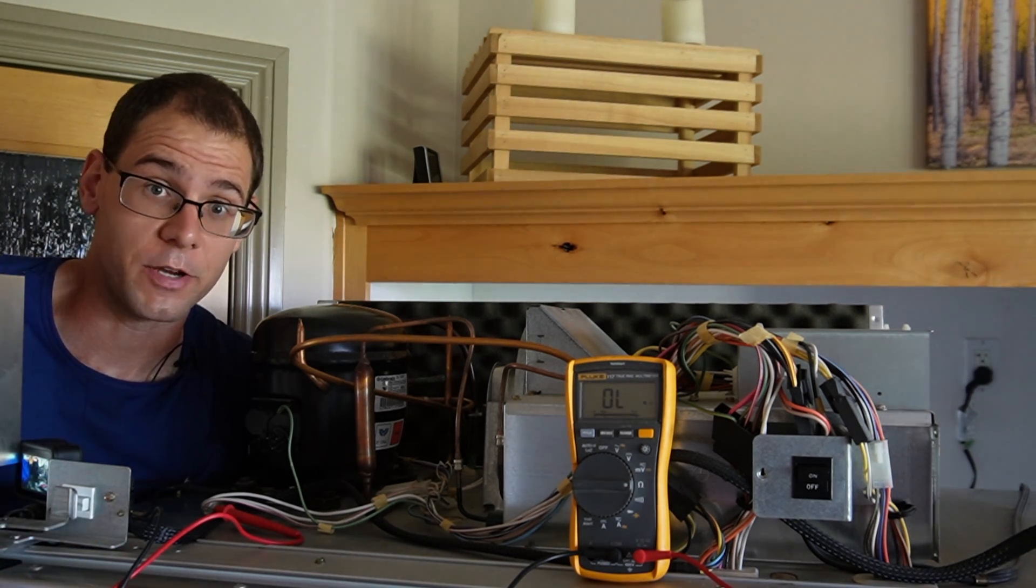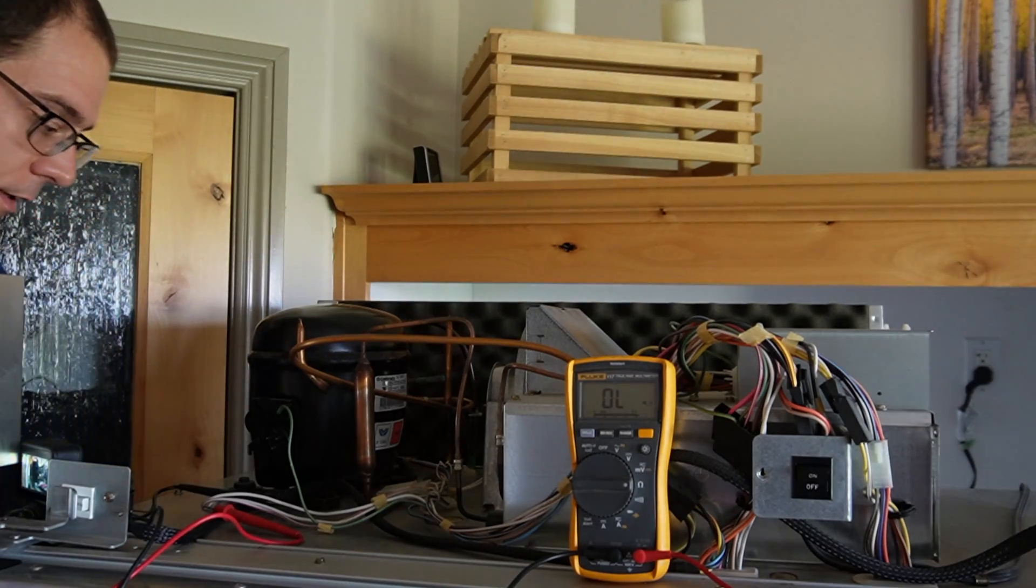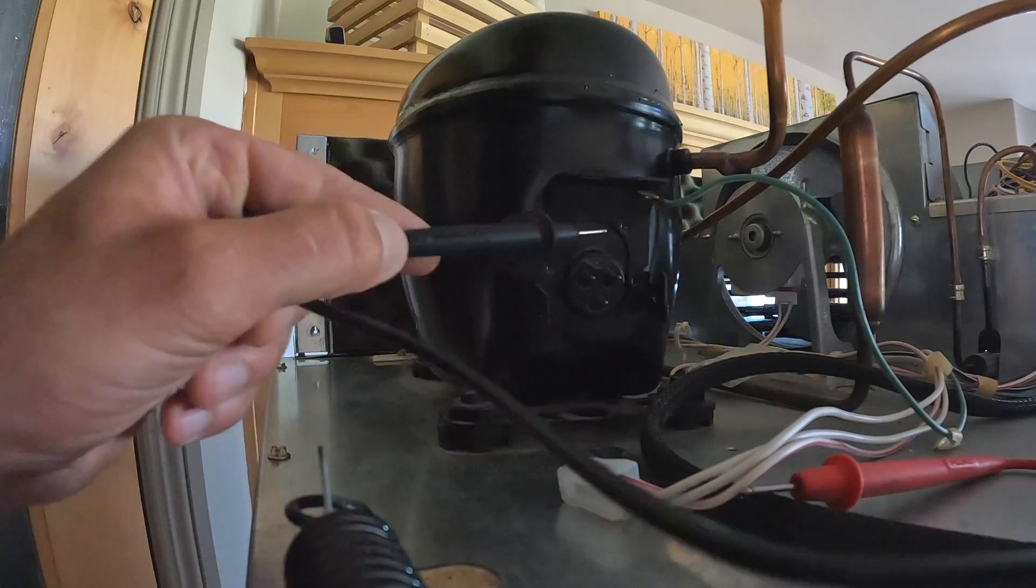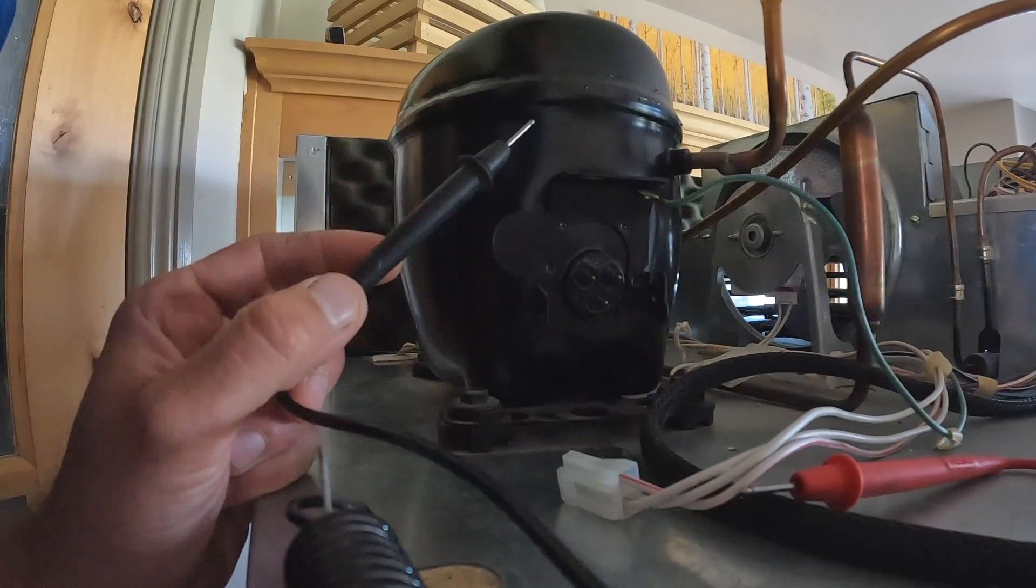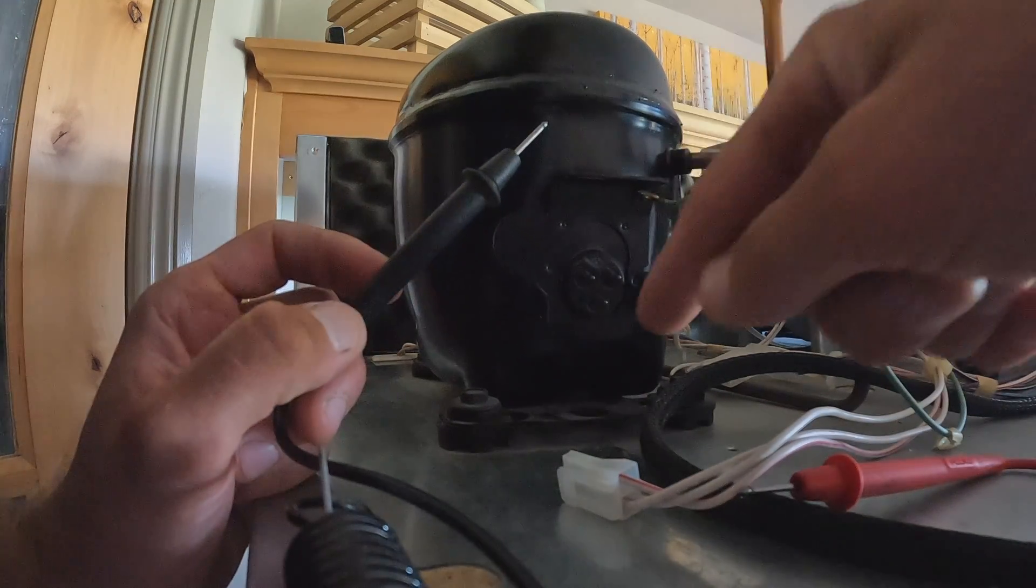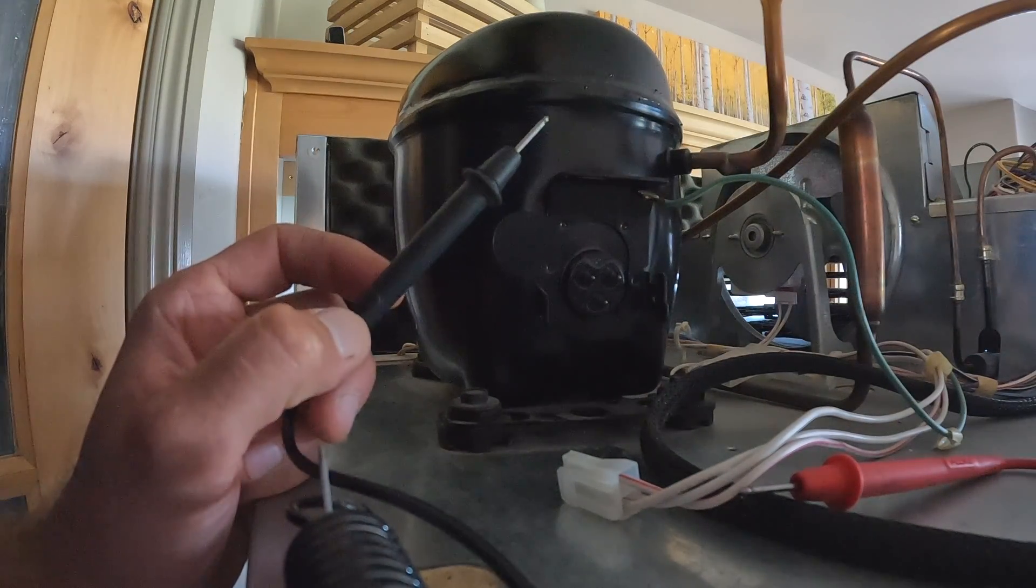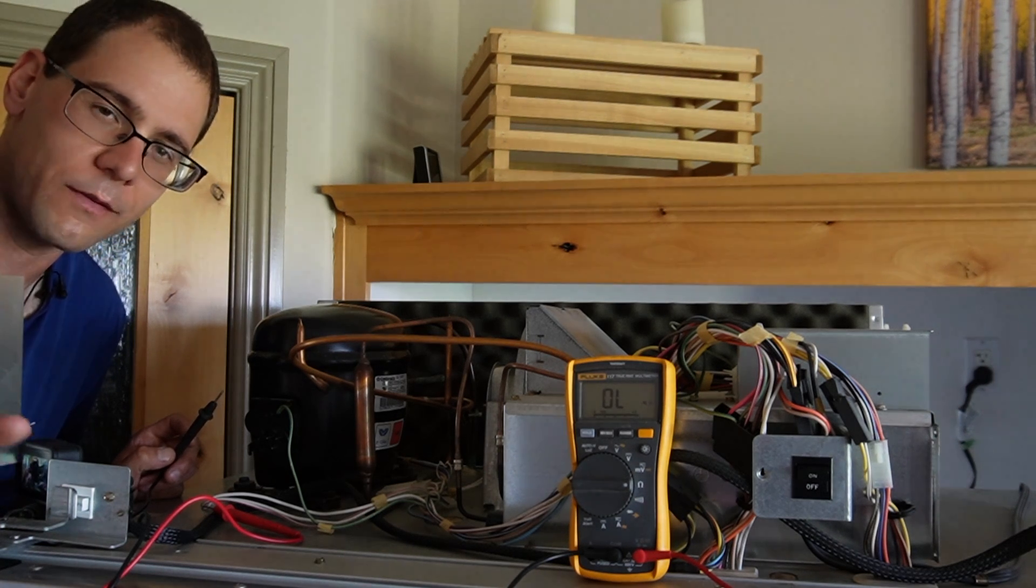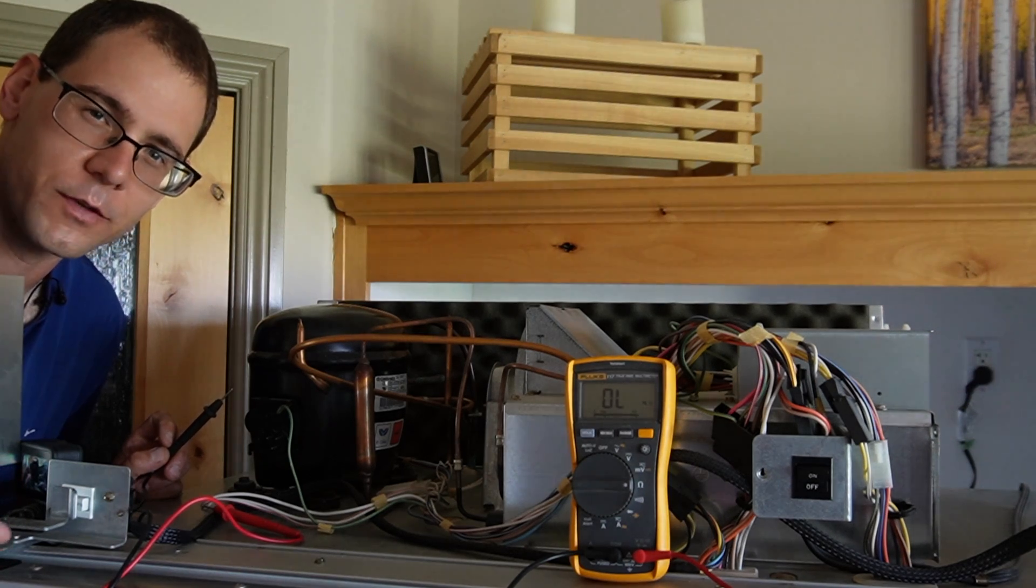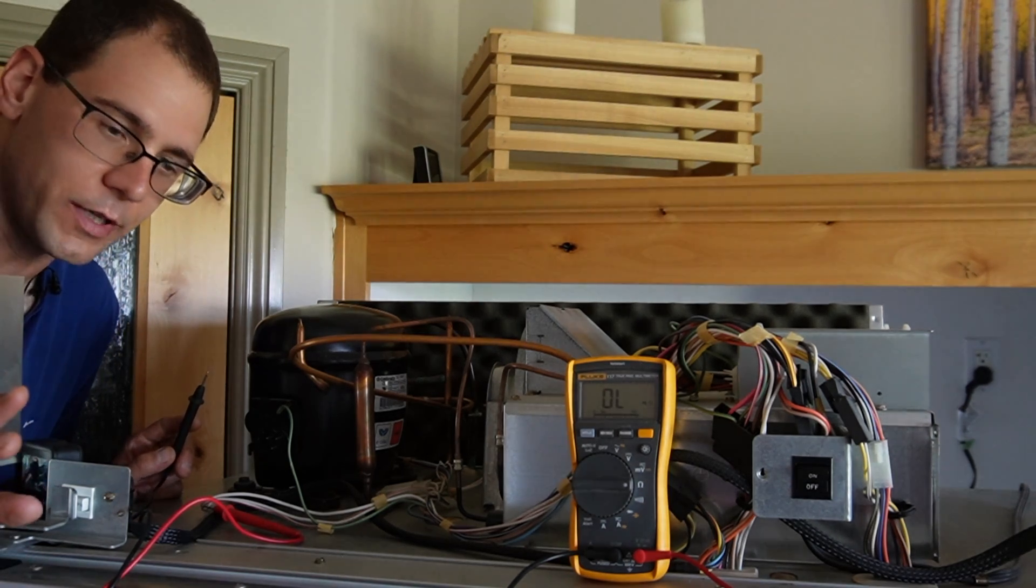I have the multimeter set up in resistance mode so we can take those measurements. Before I do, I want to mention that this Fluke 117 multimeter is a fantastic multimeter. I've had it for many years, it's extremely reliable, never had a problem with it. I'm going to put a link in the description. Let's take those measurements. The bottom terminal is our common. These top two, we have to figure out which is start and which is run by checking resistance between common and each lead. On the start winding we're looking for about 5.9 ohms, and on the run winding about 2.8.